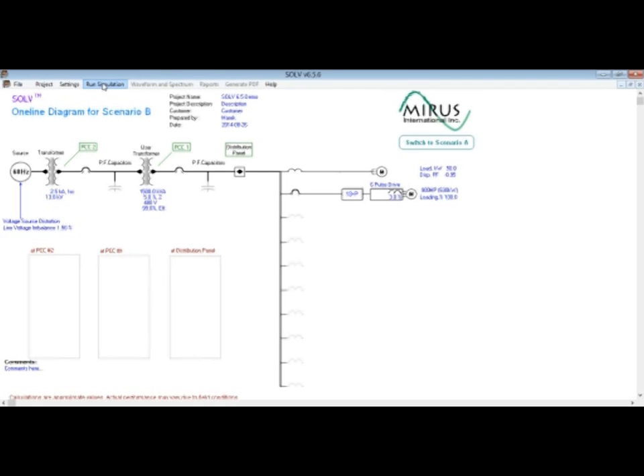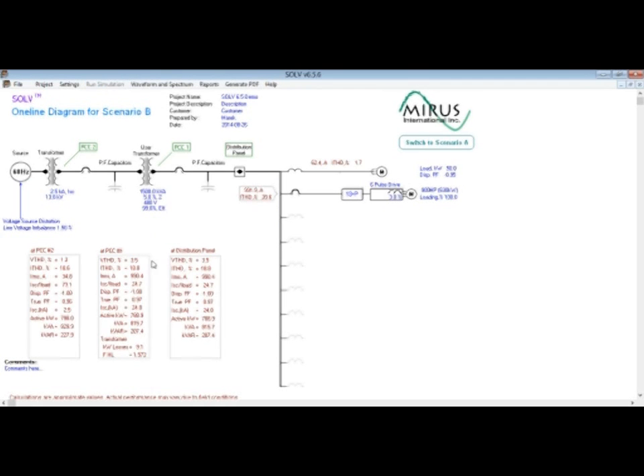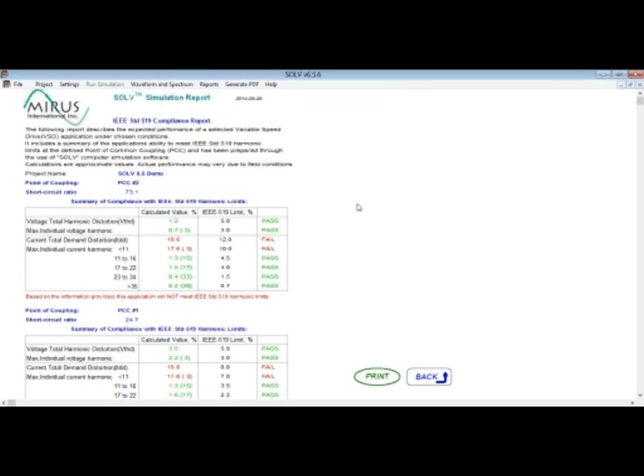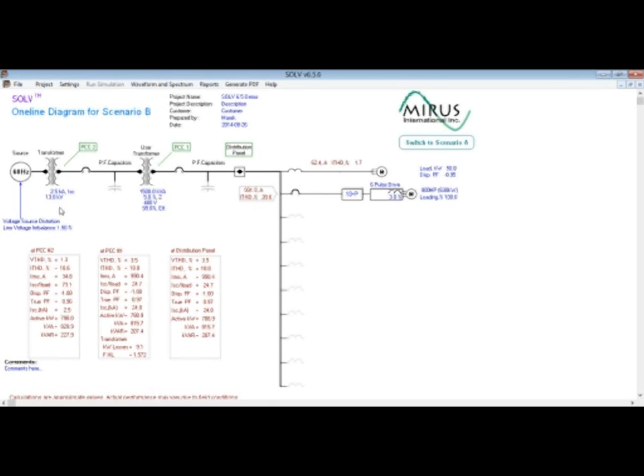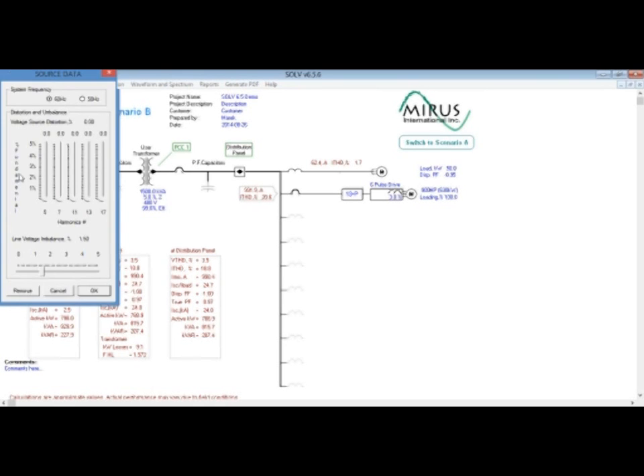So now we can run the simulation, and looking at the tables for PCC1 and PCC2, we can see that the 18-pulse drive system dropped off in performance, and the THD exceeds 18%. Going to reports and opening, we can see that we now fail the recommended limits for IEEE 519 with this solution under small voltage imbalance. So I go back. Also, pre-existing voltage distortion can cause degradation in harmonic mitigation performance.